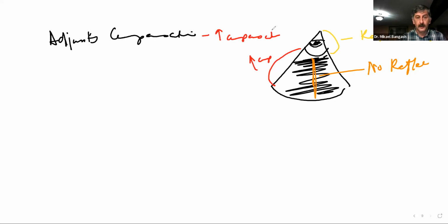Because if you get the same image and there's an option that, for instance, says decrease the compensation, that would be completely wrong. Because that was just going to make it even darker. Even if you had some slight reflections, that decrease in the compensation was just going to make these weaker reflections completely lost.